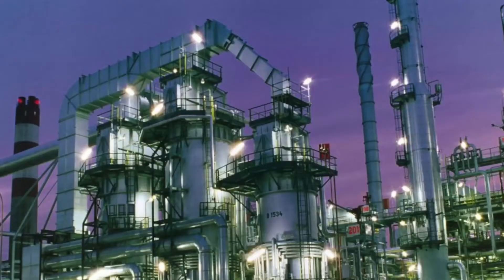The objective is to reduce the oxides of nitrogen, which we would more commonly refer to as smog. So this boiler, in addition to being highly efficient, is one of the least polluting boilers for its size. A 250 pounds per square inch, 15,000 pounds per hour boiler is on the small end of an industrial boiler — it wouldn't compare with the large boilers up in Fort McMurray in the oil sands, but it would compare favorably with what you'd expect to see at a mine or a gas compressor station, and in parts of refining operations. The technology is scalable — everything that happens here happens on a larger scale in a real industrial plant, like a pulp and paper plant or an oil and gas refinery.